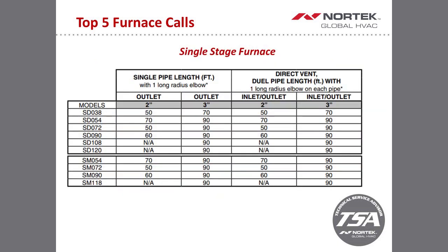So this table here is directly off of the tech spec in a single stage furnace. What I have here is the vent table, and mainly what I want to point out is what your 2-inch allowable length is along with your 3-inch. So you can see just by looking at this table, when you go to a 3-inch pipe, on most applications except the smaller BTU, you'll have 90 feet to play with. So that by far will get most applications out of the way from a piping install. You'll also have a lot more flexibility in your fittings. You'll be able to use more 90s if you have to work around some things in the home.